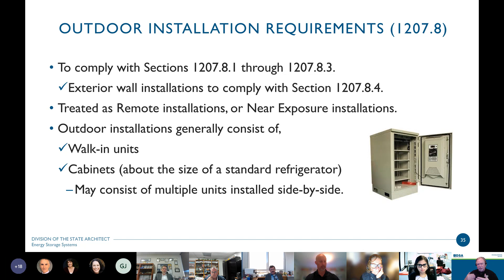So when we talk about remote installations, as I said at the beginning, I think that DSA will see those installations that tend to meet more of the near exposure, and this is why. Remote installations are those where the energy storage system is located more than 100 feet from buildings, lot lines, public ways, any stored combustible materials, hazardous materials, high pile stock, and any other exposure hazard. So you can imagine the impact on an existing smaller campus in trying to put something 100 feet away from all of these.